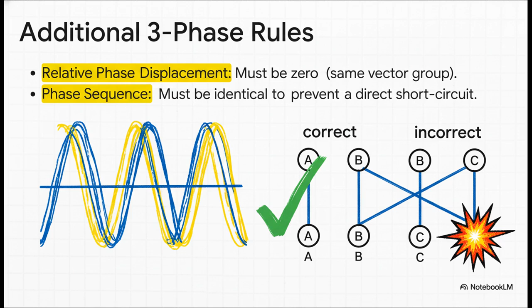The second rule, though, is even more serious. The phase sequence must be identical - ABC on one has to match ABC on the other. If you get this wrong, say you connect phase A to phase B, it's not just a small problem, it's a direct, massive short circuit. The result is instant, and it is not pretty.